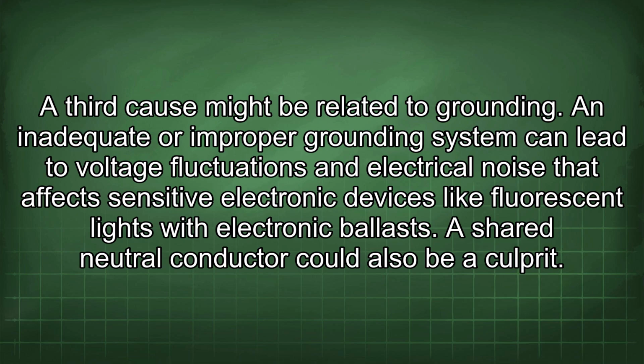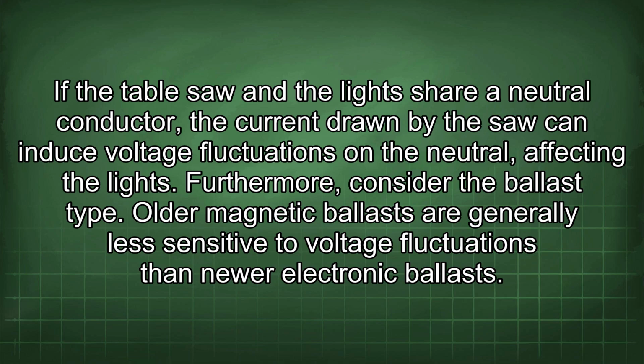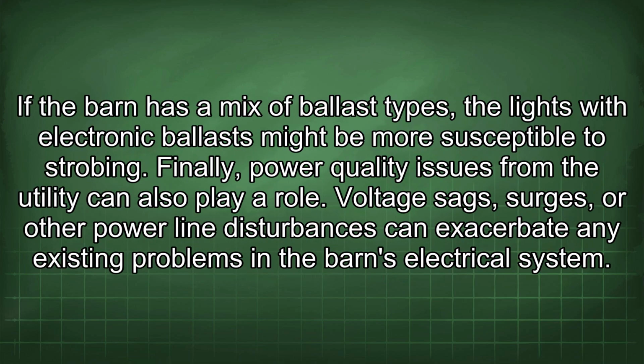A shared neutral conductor could also be a culprit. If the table saw and the lights share a neutral conductor, the current drawn by the saw can induce voltage fluctuations on the neutral, affecting the lights. Furthermore, consider the ballast type. Older magnetic ballasts are generally less sensitive to voltage fluctuations than newer electronic ballasts. If the barn has a mix of ballast types, the lights with electronic ballasts might be more susceptible to strobing.